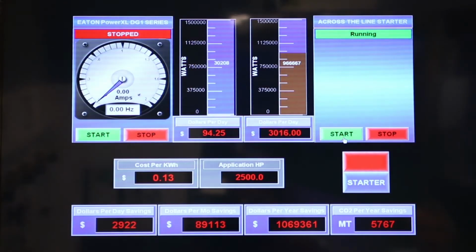So Dan, why don't you quantify for us what the amount of energy savings might be in a situation like this? Sure, Lee. An induction motor runs at 60 hertz at its full rotational speed. If you cut that speed in half, you run the drive at 30 hertz, for example, it's going to run at half speed. Now you might think you're going to save half the energy, but in fact you save more than three quarters of the energy. You use a half times a half times a half, or about an eighth of the energy. So if you took a 100 kilowatt load, you'd use about 12 and a half kilowatts to do that same amount of work. That's the advantage of using the drive versus the valves and dampers. Yeah, that's a significant savings.